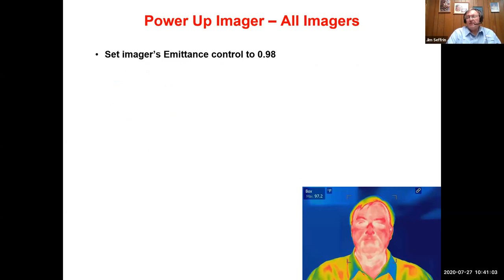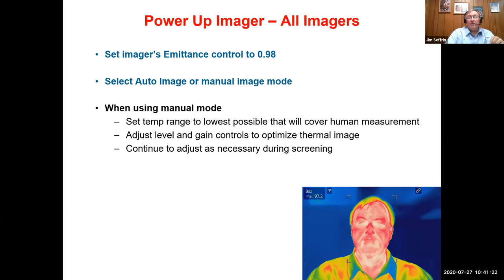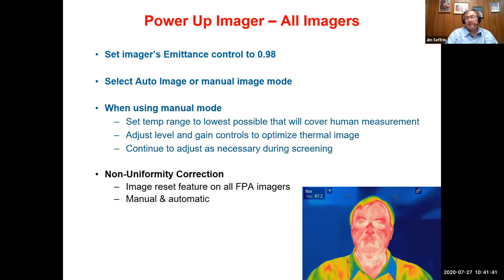Next, you want to set your imager's emittance control to 0.98. Human skin has a very high emittance, and it's generally agreed worldwide that it's around 0.98. So you set your imager's E control to 0.98. You can then select auto image or manual image mode. When you're using manual mode, set your temperature range to the lowest possible that will cover human temperature measurement. It's typically going to be range one or the lowest temperature range. You adjust your level and gain controls, or level and span if you prefer, to optimize the thermal image, and continue to adjust as necessary during the day as you are conducting your screening.